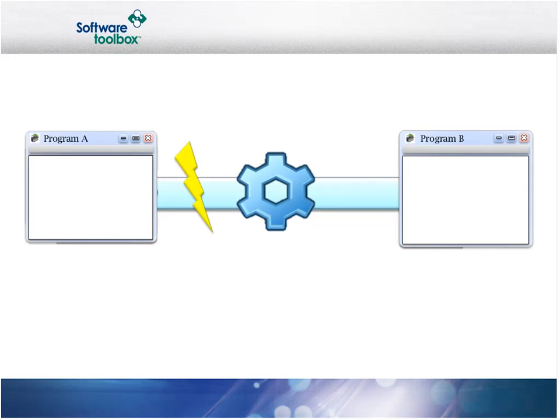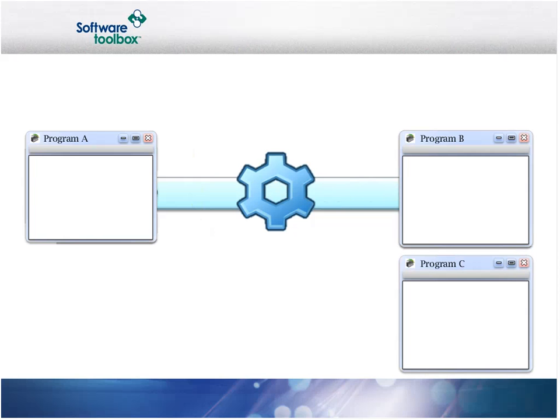This also means that losing the connection between the tunnel data hubs won't cause your OPC client to hang while waiting for a response, because your OPC client is just talking to the local data hub's data store, which is constantly refreshed with data from the remote server when the connection is up. When the connection goes down, it'll automatically resume when the network connection is restored, and while it's down, you'll know in an orderly fashion. Wynn will give you the whole how of that in a few moments.